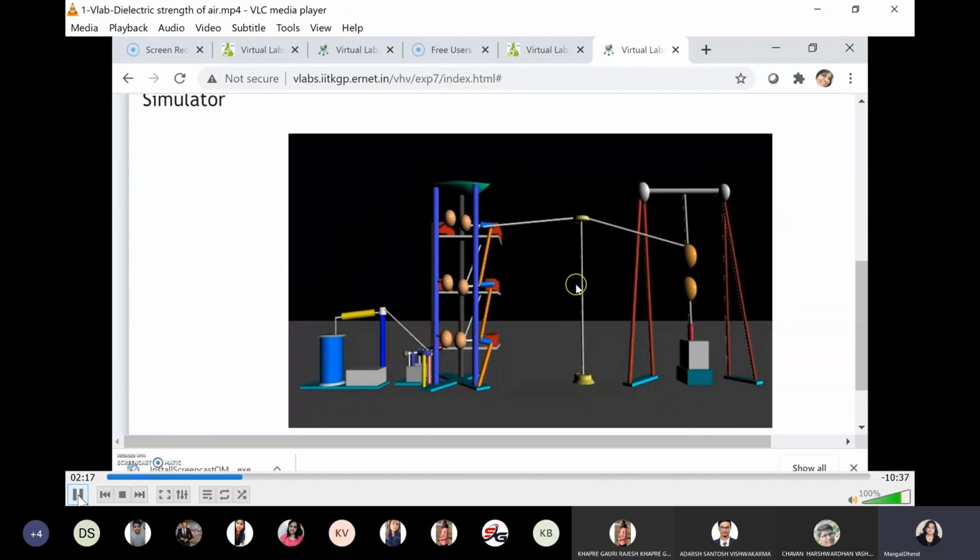So this part is changed. Here, instead of using a step-up transformer, an impulse generator is used, which will generate an impulse waveform. Now you don't know, but you can still think of it as a high voltage. Lightning, you know, when lightning occurs, that waveform is an impulse voltage. So that is the impulse generator. It will generate a lightning waveform, and that will be applied across the sphere gap, and you can find out at what gap distance it breaks down.